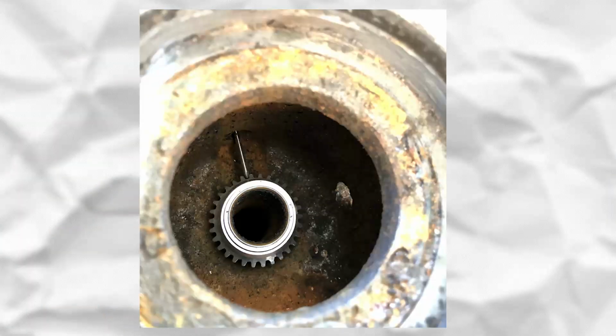The cross-section of releasing is calculated by some special software, so as an instrument engineer, you must have the ability to calculate the discharge area and choose the best selected area for a PSV. There is a ring around the PSV seat known as blow-down ring. It is always locked by a pin accessible on PSV body.